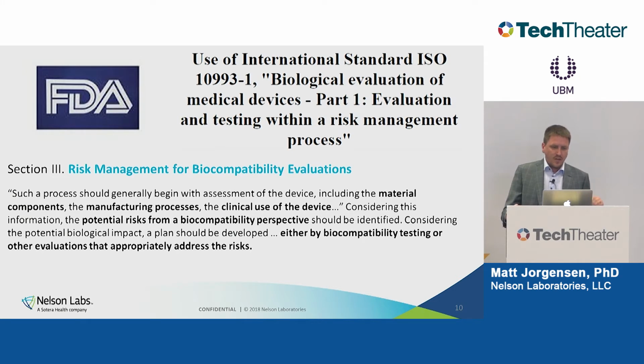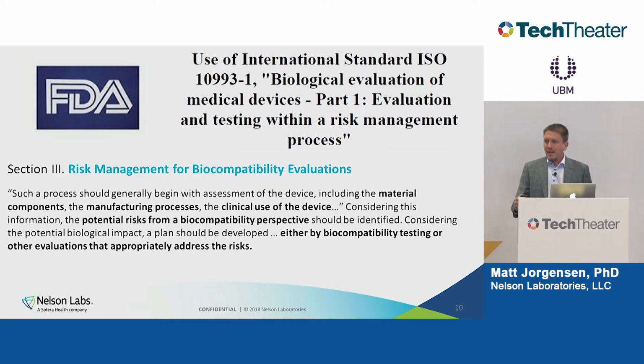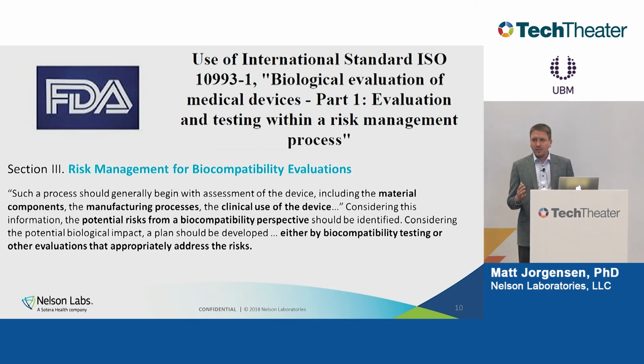This is all coming out of the FDA's guidance document, and I want to read this one segment because I think it's pretty important. It says, for the risk management for biocompatibility evaluations, such a process should generally begin with an assessment of the device, including material components, the manufacturing processes, the clinical use of the device, and then considering this information, the potential risks from a biocompatibility perspective should be identified. Considering the biological impact, a plan should be developed, either using testing or other evaluations as necessary, to appropriately address the risk.